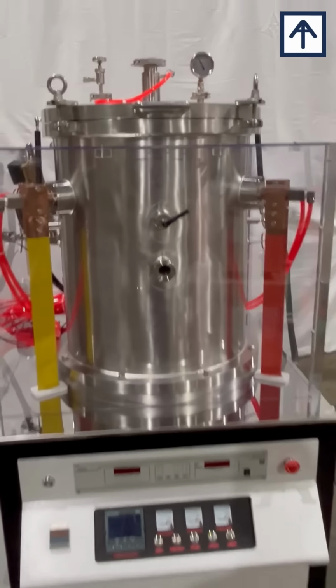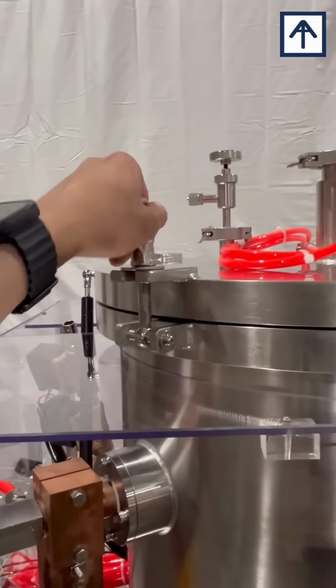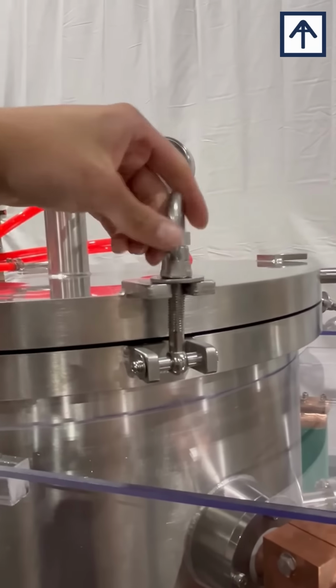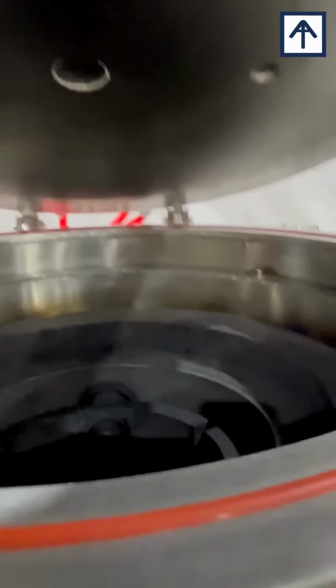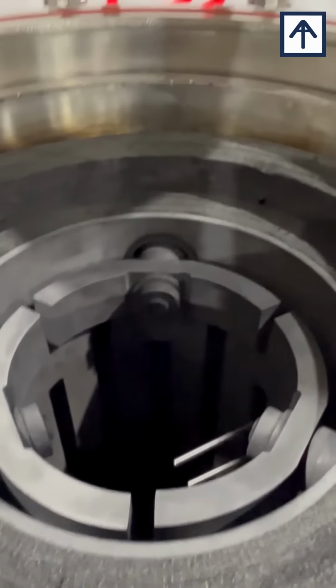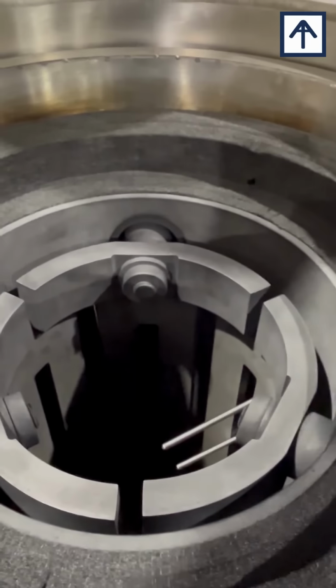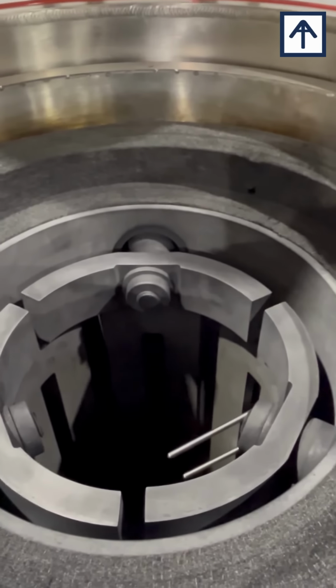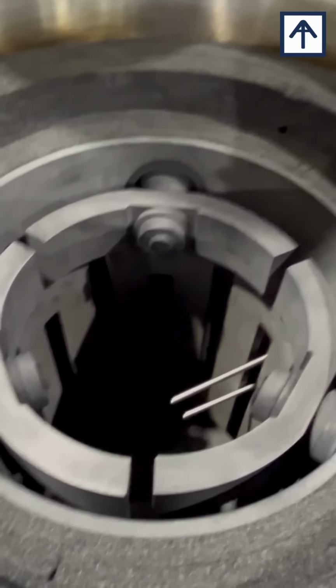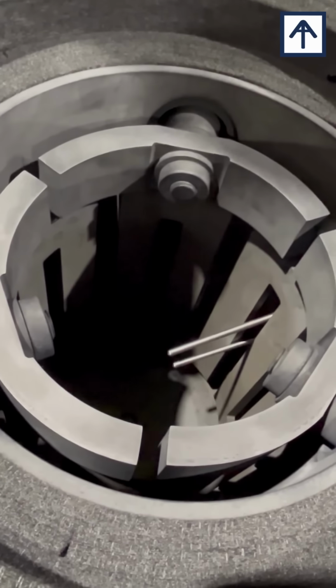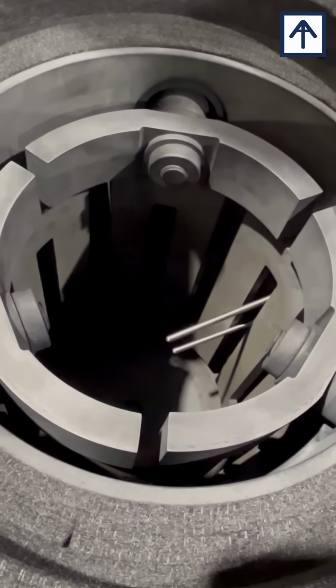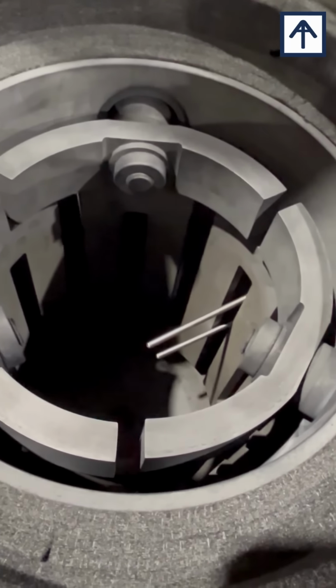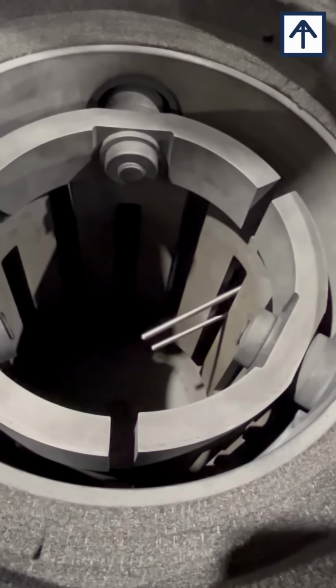And then let me show you the lid. So the lid is bolted down with 4 of these bolts. So you just unthread or just open them, and then you can lift the lid. It comes with another secondary lid on the inside, which can be taken off, and then you can see the graphite heating elements as well as the graphite enclosure. You also get a stand for your graphite crucible in there. That's standard with all of our units, as well as you can see the primary and the secondary thermocouples in there.